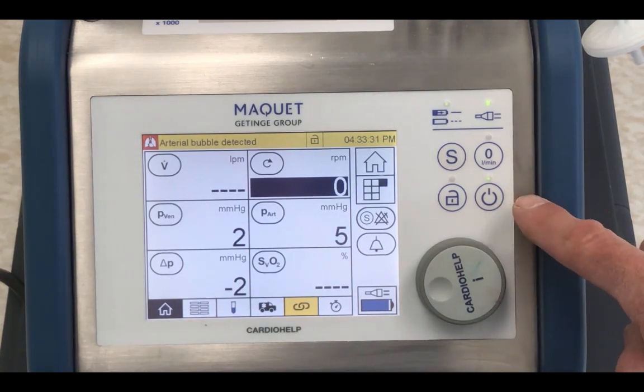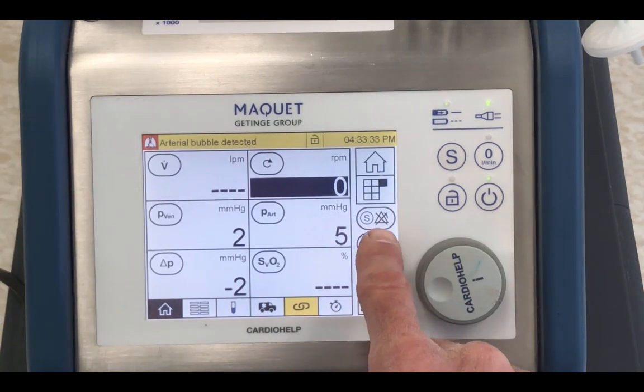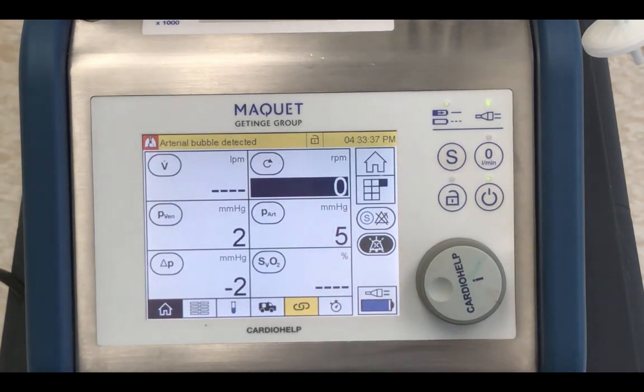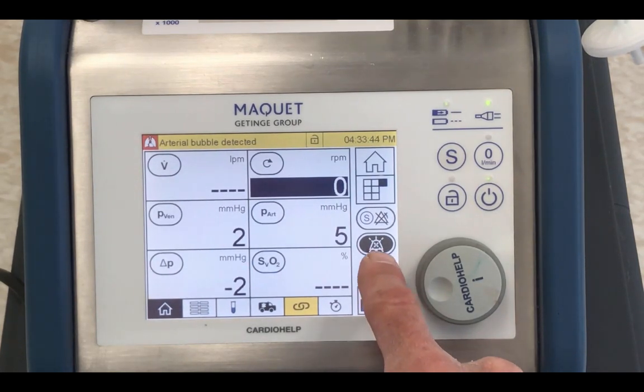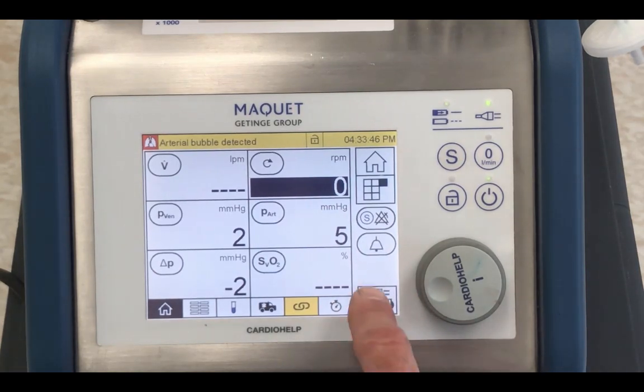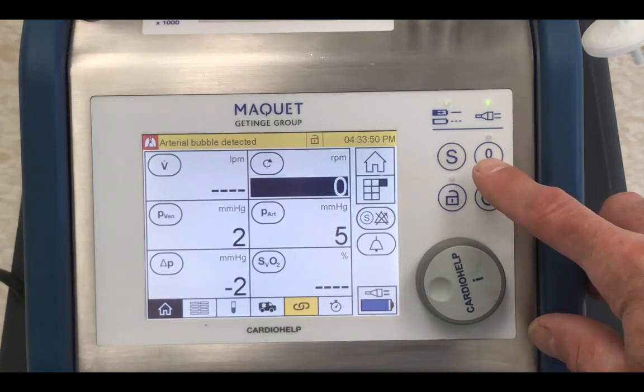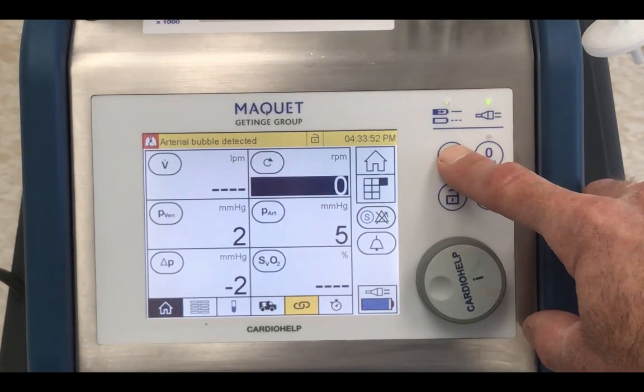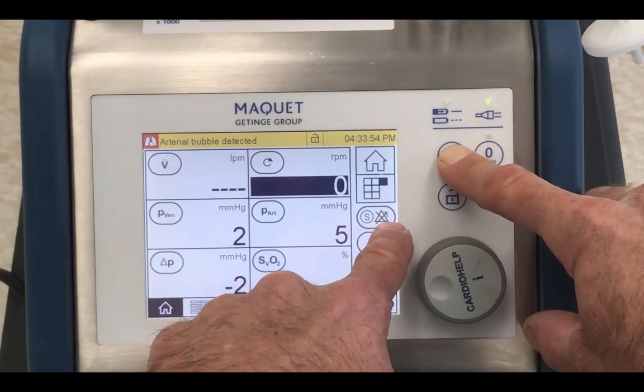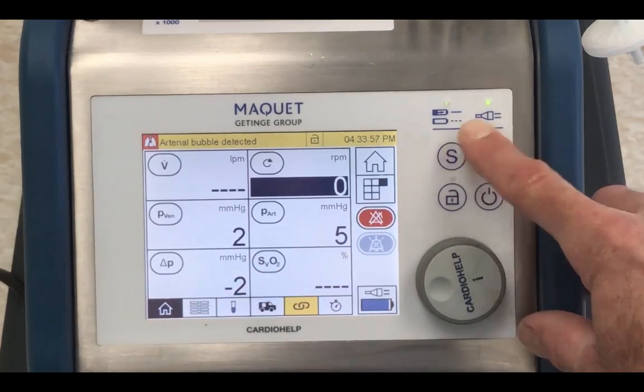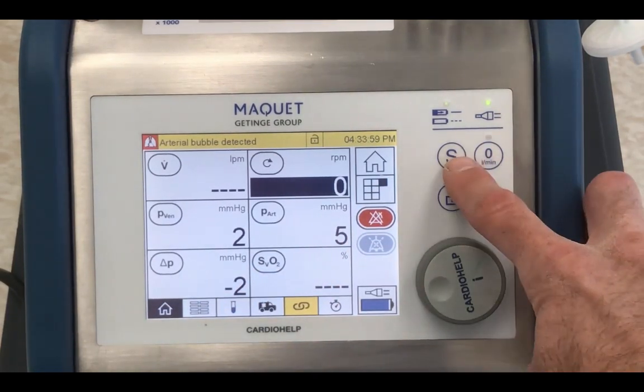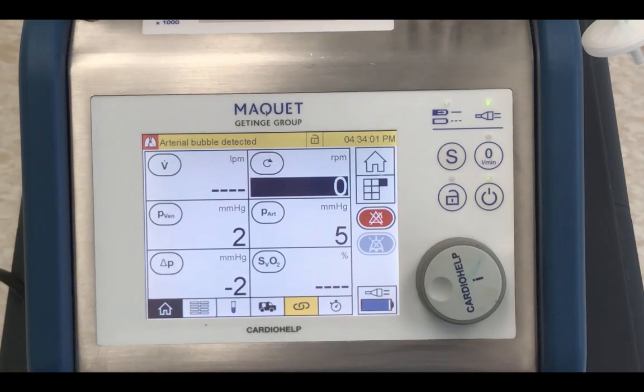We could silence it with our typical medical silence alarm here, and now it should stop beeping for a little while, but it'll eventually kick back on again. We're going to be talking for a while, so I don't want to have to keep pressing the normal silence alarm that you find on every medical device. And we're going to do a global override. We're going to press the S, and then we're going to press this button here, and the two of those together, holding this down and then pressing those, it gives a global override.